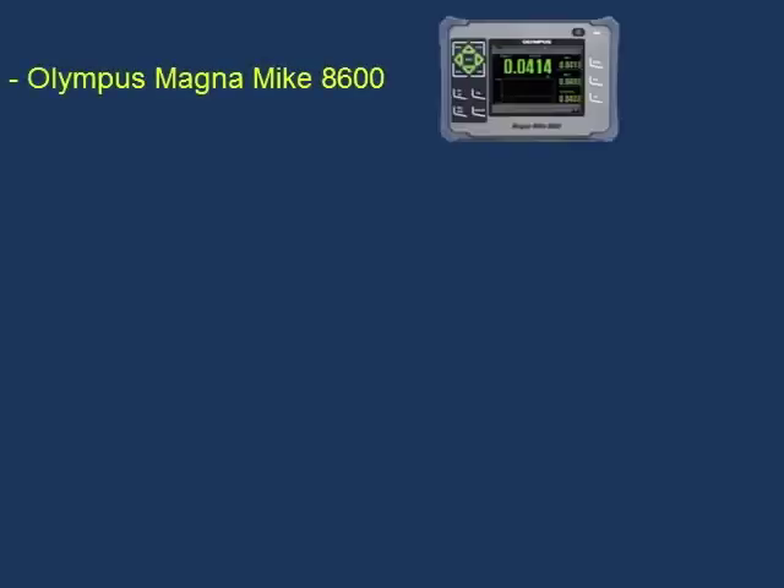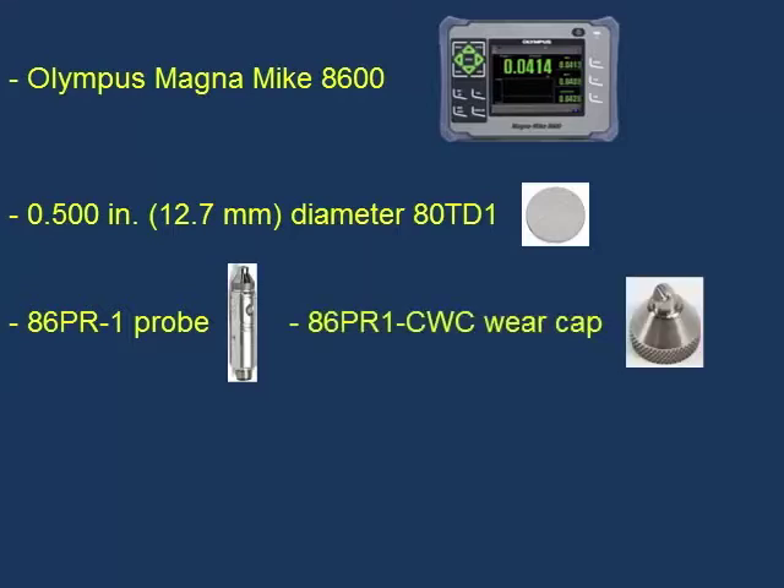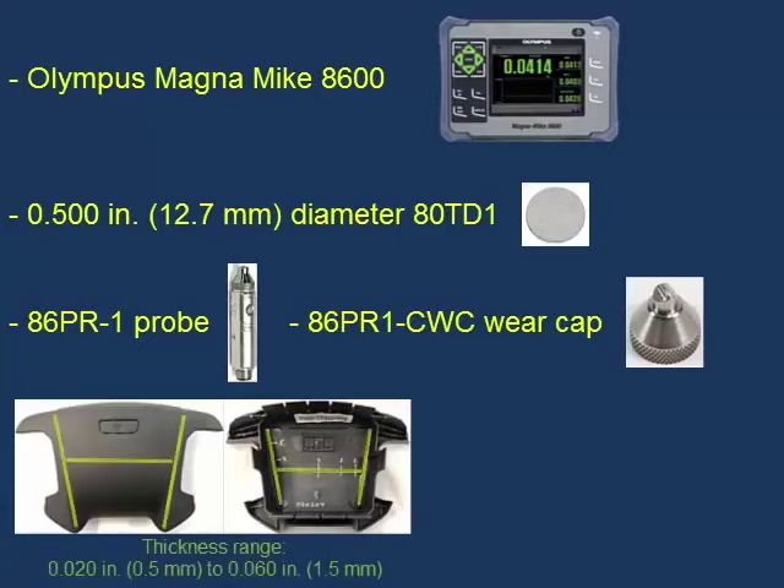In this demo, we will show how to calibrate the Olympus Magnamike 8600 using the half-inch or 12.7 millimeter diameter 80TD1 flat target disc. We will then use the disc target to measure the thickness of tear seams on an automotive airbag cover. The thickness of the tear seams ranges from approximately 0.020 inches or half a millimeter to 0.060 inches or one and a half millimeters.